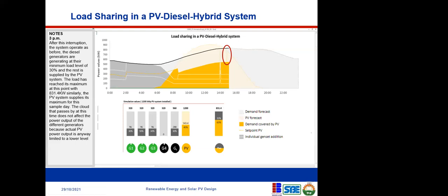Sorry, if I may ask. Looking at us running 3 generators, I'm assuming they have to be on the same bus and they have to be synchronized. So are we also bringing the source of the inverter into the same bus for the controller to be able to pull these things together? Are we synchronizing the inverter with the generator sources?